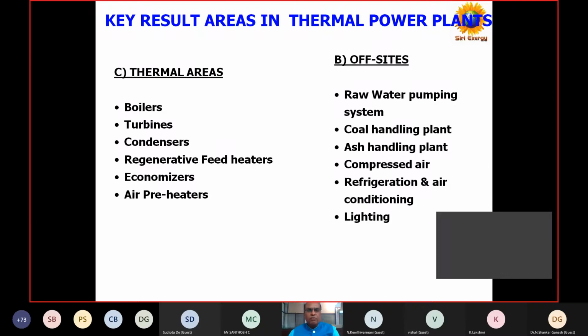Next is the turbine - we'll be doing turbine efficiency, either HP turbine, LP turbine, or the intermediate IP turbine, and also next is the condenser. Whatever LP steam is condensed there, we can recover the condensate back to the boiler and improve the overall performance of the turbine system. Next is feed heaters.